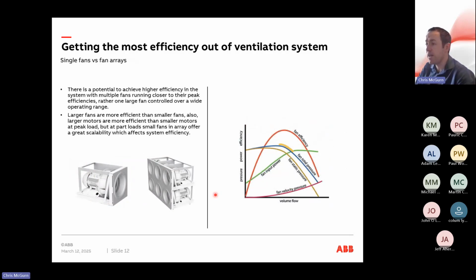And again, in some fan array systems, in HVAC systems, sometimes companies use AHUs. There's potential to achieve higher efficiency in the system with multiple fans running close to their peak efficiency rather than one large fan controlled over a wide operating range. So this is just telling you to be careful of the design of the system you're looking at. It's not always better just to put a big motor and a big fan on to run a specific system. Sometimes it's better to break it down into, in this case, 6 different fans that are easier to control at the peak efficiency load and will provide improved efficiency savings.